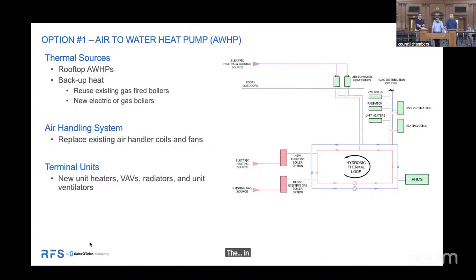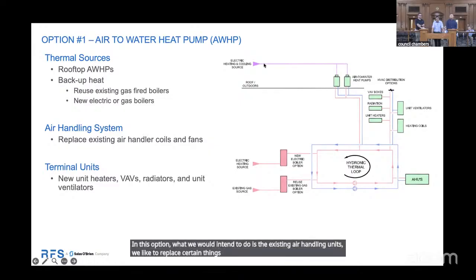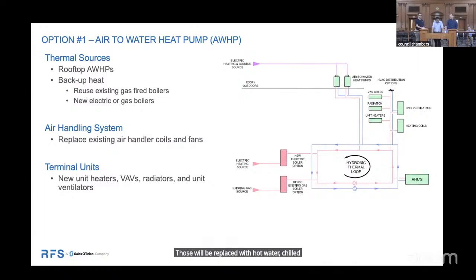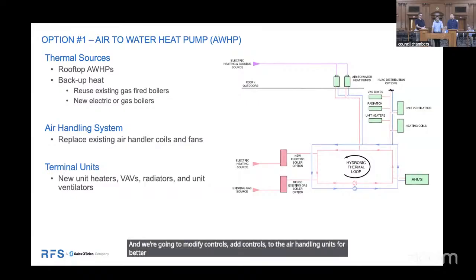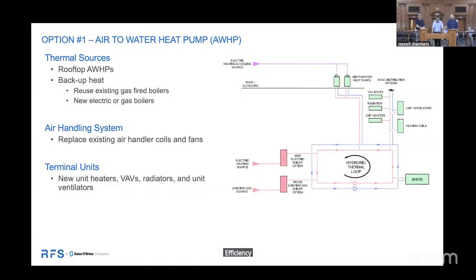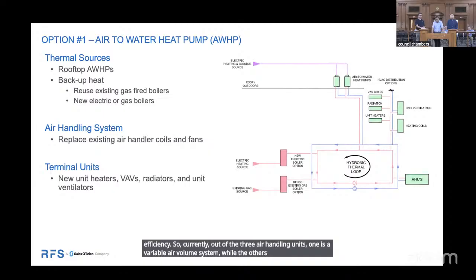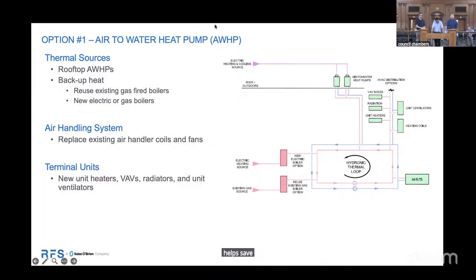In this option, what we intend to do is replace certain things in the existing air handling units. For example, all of these existing air handling units have refrigerant coils in them. Those will be replaced with hot water and chilled water coils. And we're going to modify and add controls to the air handling units for better modularity and efficiency. Currently, out of the three air handling units, one is a variable air volume system, while the others are constant volume. Constant means the fan is running all the time, using a lot more energy, so introducing intelligent controls will help save us energy.